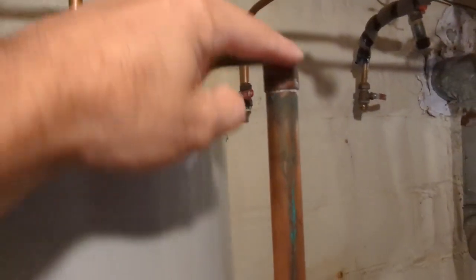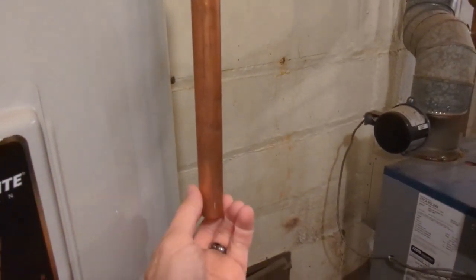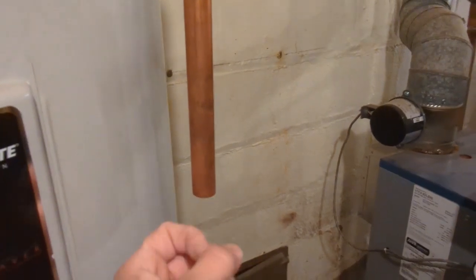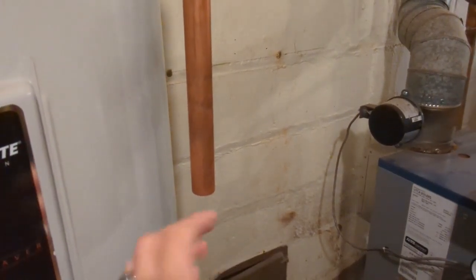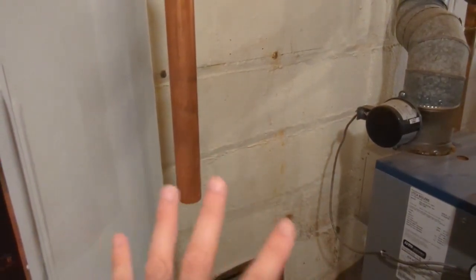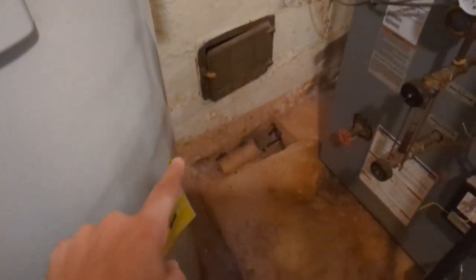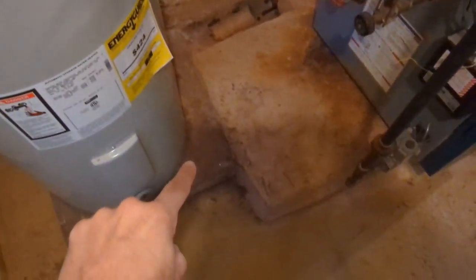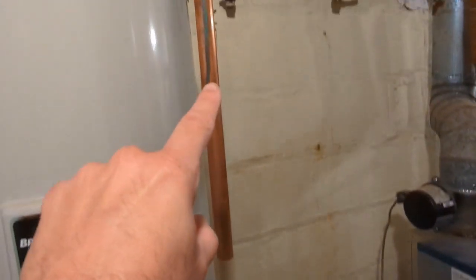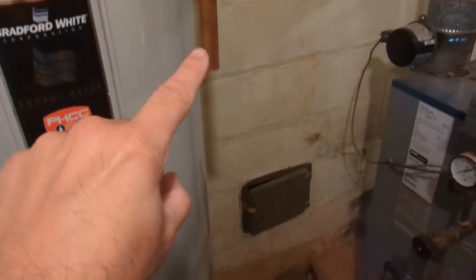So when this valve discharges, it's going to create a lot of pressure. Steam and hot water are going to flow with great force out of this piping. So you don't want to be around when that happens and have this piping around your eye level or where, you know, it can impact a person. So that's why they want it discharging about 4 inches from the floor. So not a big deal. We'll make a recommendation that they install a pipe just in case this were ever to come into play. Nobody gets hurt.